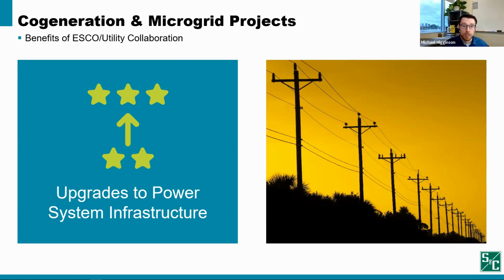Other upgrades can include switchgear and breaker upgrades to interrupt increased short circuit levels. As I mentioned previously, short circuit levels often increase when we're interconnecting cogeneration or microgrid generation, as well as storage.